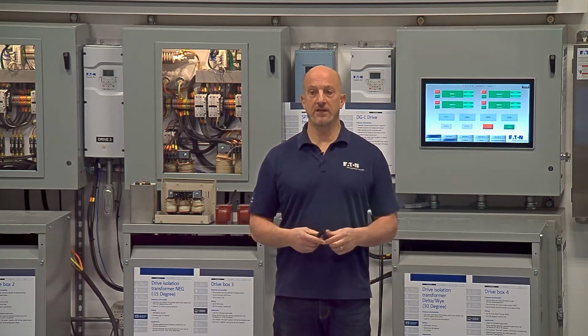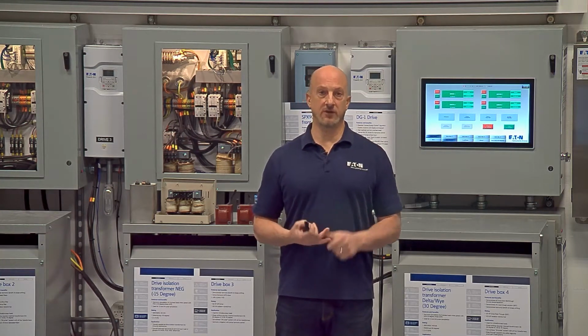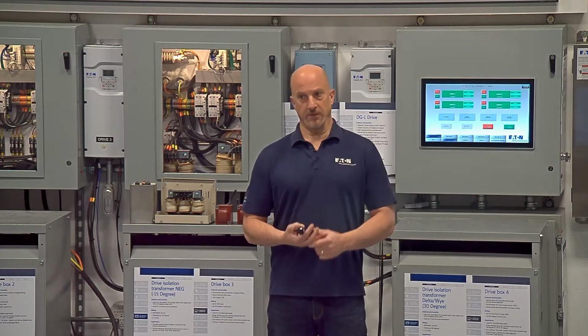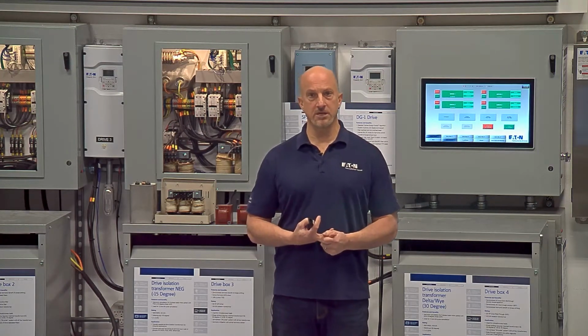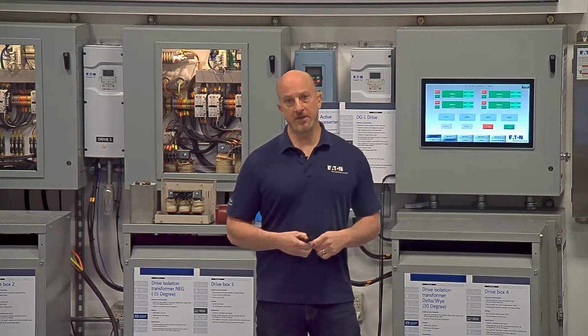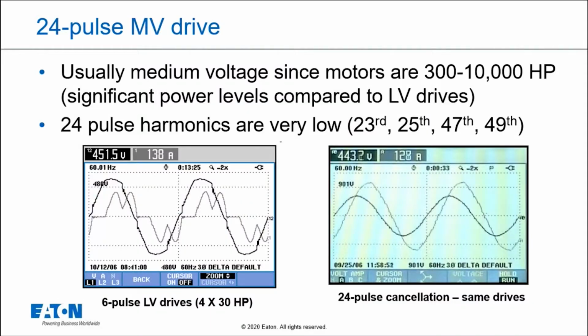So again, the benefit is usually these are very large drives, 300 to 10,000 horsepower motors. And so let's take a look at a picture of how that cancellation works. In the power quality lab here, we used 30 horsepower drives, and we ran them all together without any cancellation. And then we ran the same exact scenario, but with 24 pulse cancellation. And take a look at the waveform of the current, which is the taller one on the right-hand picture. You can see that the waveform almost looks purely sinusoidal.